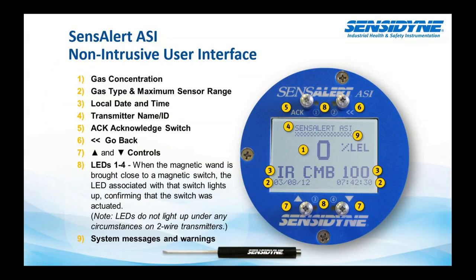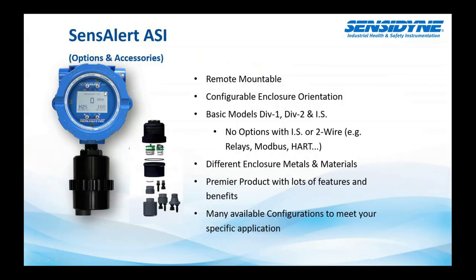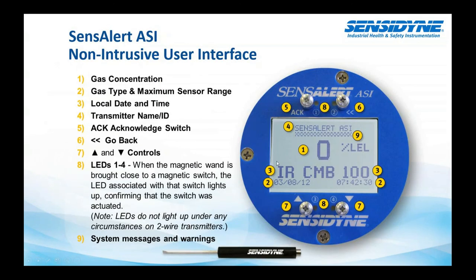The SensAlert ASI, this is actually a screenshot of the faceplate here. And it's got a lot of data that we display here: gas concentration, gas type, and maximum sensor range, local date and time, transmitter ID number that the user inputs into it, acknowledge switches, go back and up and down arrows. The up, down, and acknowledge are all controlled by a non-intrusive magnetic wand. So these screw points here are actually magnetic switch points. You have your acknowledgement, your go back, and your up and down to navigate through the menus. Every time you wand over one of these, you'll see this little LED light come on to acknowledge that you have triggered that switch.